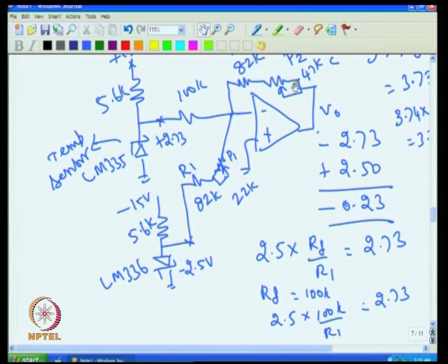Here we assumed this and this ratio is 1. If the ratio is different, say 1.1, then I have to multiply 7.5 into 1.1 and put it here, but we have taken it as close to 1. So, you may have 0.75 degree error. This can be plus or minus. For example, if this temperature drift is plus, then it will go reducing, if it is minus it will be increasing.